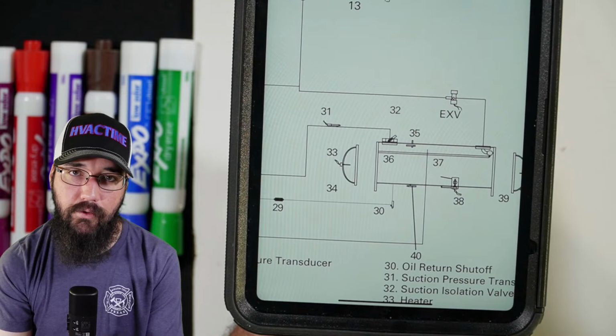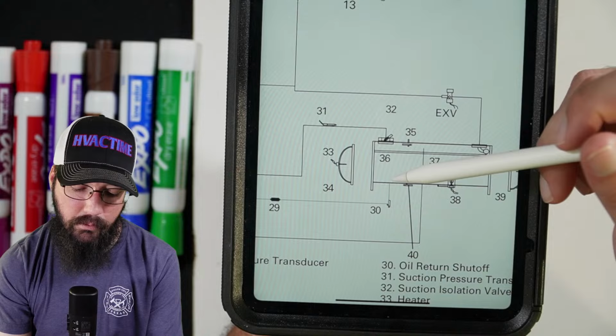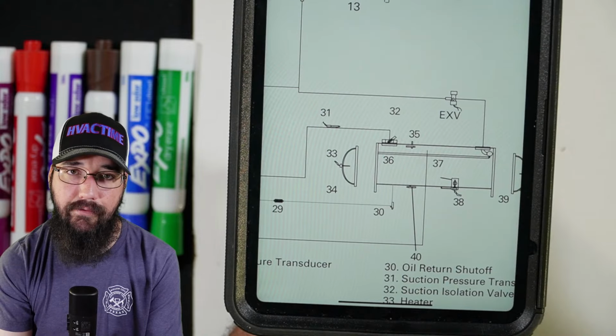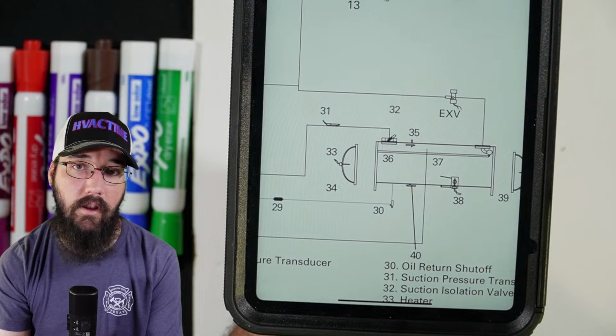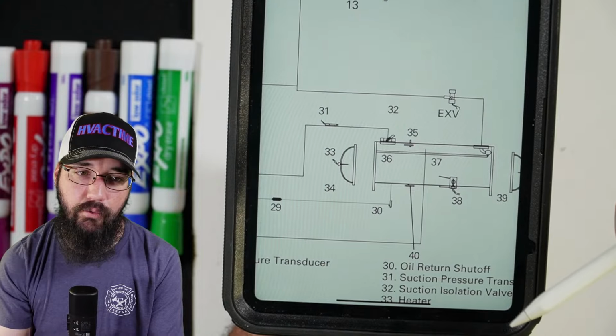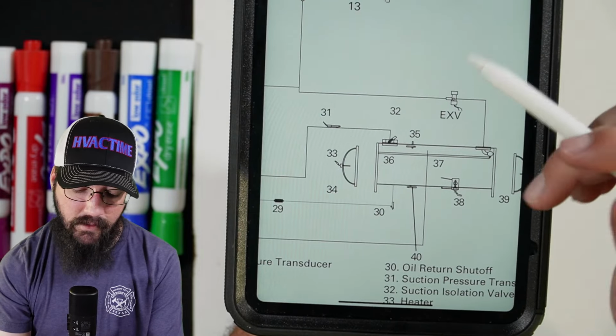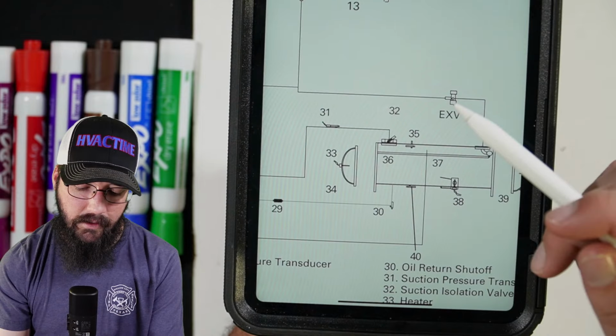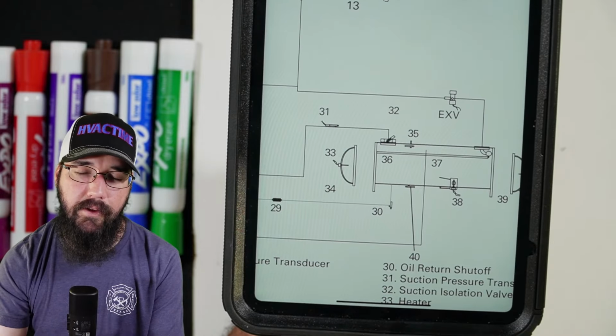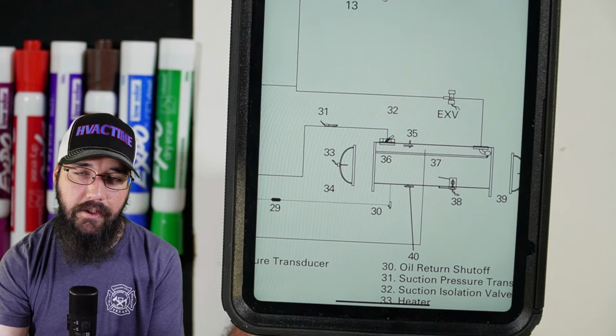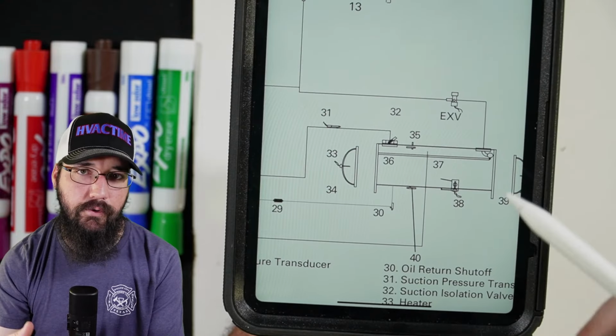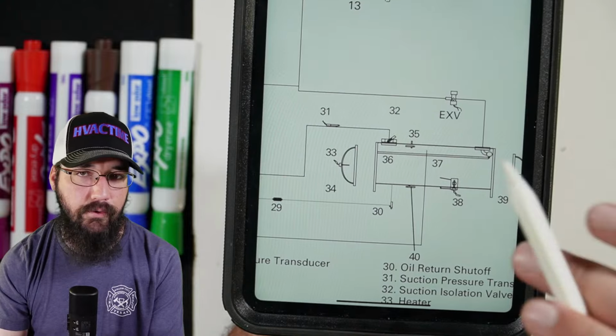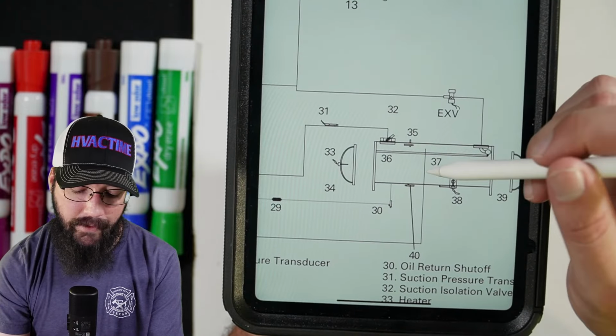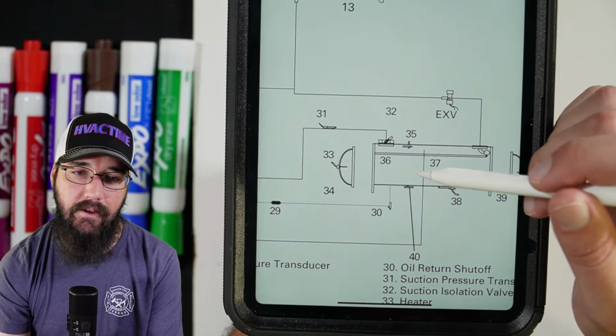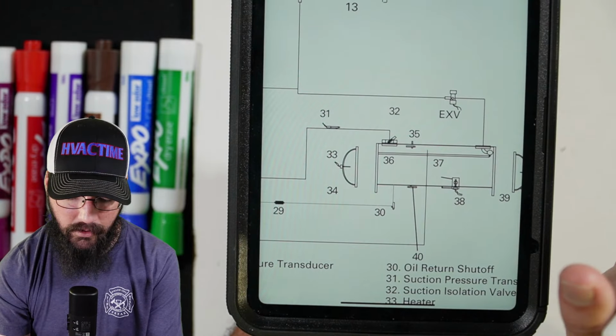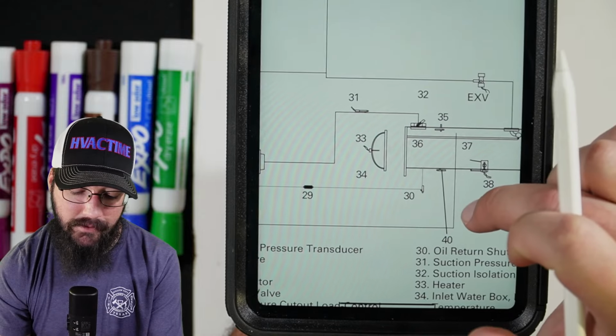We have to do something about that, because that oil will float on top of our refrigerant. It affects our heat exchange. Eventually it will oil log the evaporator, which will prevent us from exchanging heat, is what I meant to say. We'll start having superheat issues, oil level control issues. All that will begin when we start having oil stack in the evaporator. It causes a lot of issues for us, so we need to do something about that oil.